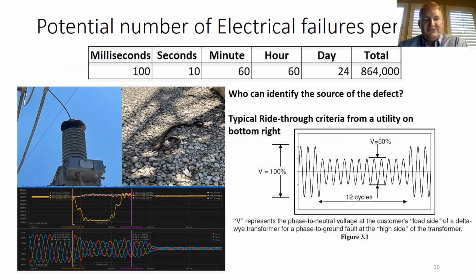So what was the cause of this failure? Here you have the line coming off the feeder to the transformer. Can anybody identify what that was right there? It looks like a stick. This caused one of the largest shutdowns in Texas, and it's actually a snake. This guy was crawling around up here, and he touched two different points at the same time - of course he fried himself, but he also shut down probably close to $150 million in production in one day.